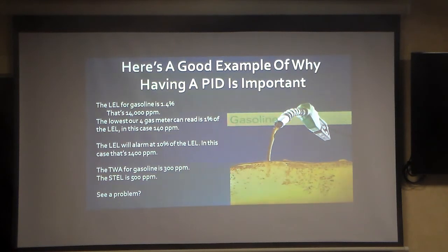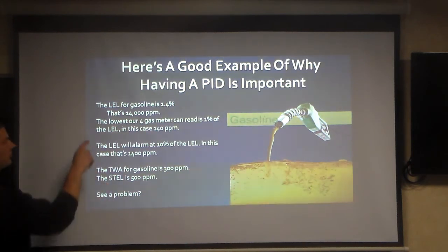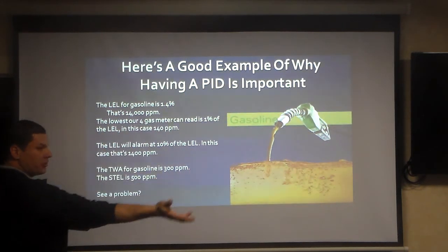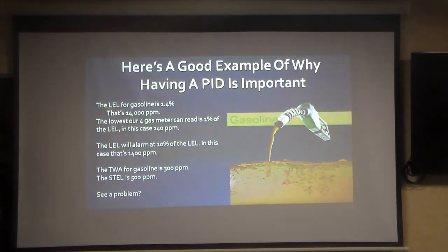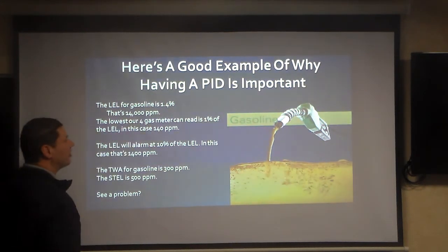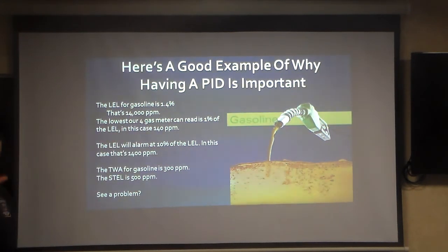it's more volatile. There's a low concentration of it, right? That's to tell us at the bottom, the UEL, right? Or the LEL, I'm sorry. So remember that, right? So if we take 1.4%, we turn it into parts per million, that means 14,000 parts per million, right? 1% is equal to 10,000 parts per million. So far, are we good? Okay. The lowest our 4-gas meter can read, right? The LEL on our 4-gas meter, what's the lowest it goes? When you read it, what does it say on there?